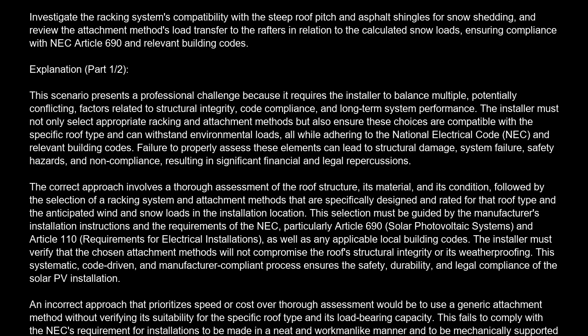The correct approach involves a thorough assessment of the roof structure, its material, and its condition, followed by the selection of a racking system and attachment methods that are specifically designed and rated for that roof type, and the anticipated wind and snow loads in the installation location. This selection must be guided by the manufacturer's installation instructions and the requirements of the NEC, particularly Article 690, Solar Photovoltaic Systems, and Article 110, Requirements for Electrical Installations, as well as any applicable local building codes. The installer must verify that the chosen attachment methods will not compromise the roof's structural integrity or its weatherproofing. This systematic, code-driven, and manufacturer-compliant process ensures the safety, durability, and legal compliance of the solar PV installation.